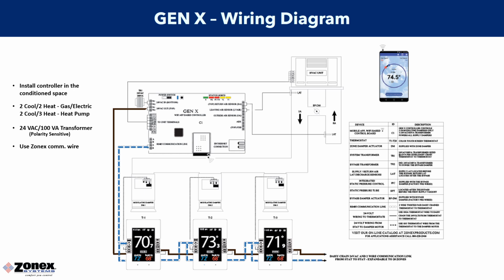Each thermostat will control its own damper using 18-3 thermostat wire. You will wire from your MC, RO, and RC terminals from your subbase up to your actuator and land them according to their call out. So MC, RO, and RC.